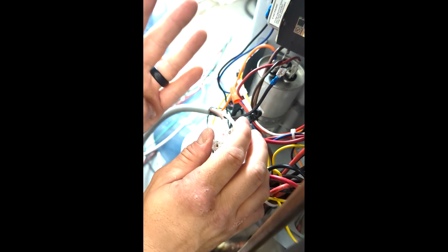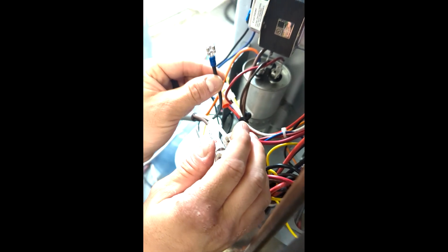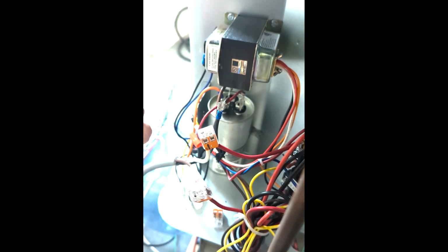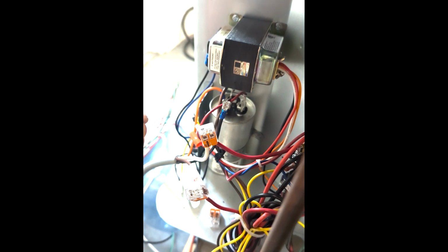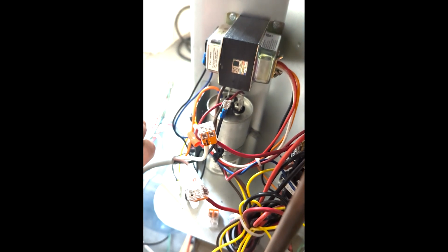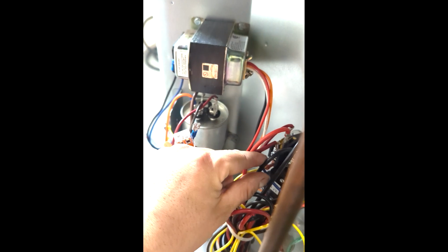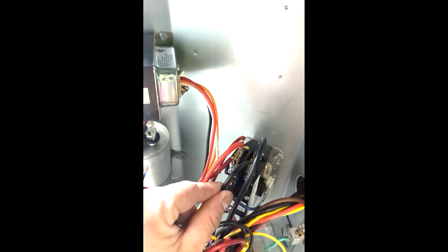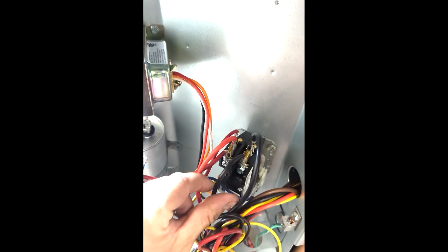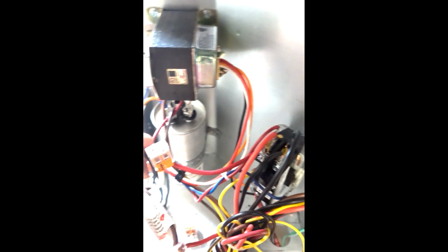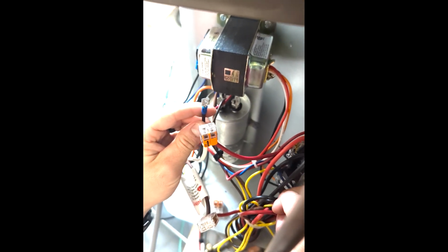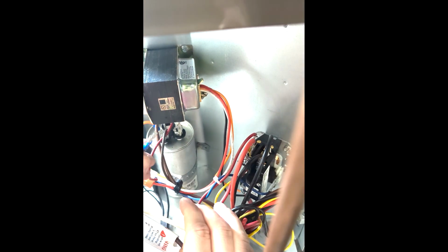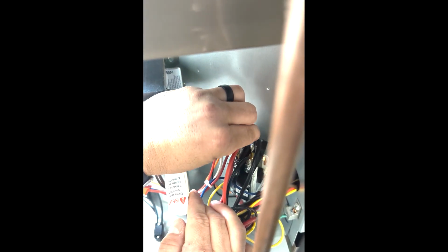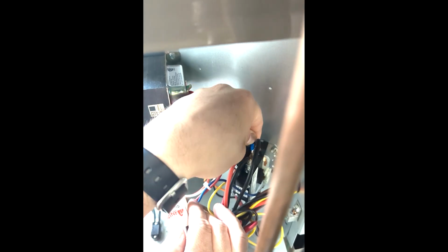Now, out of the four wires, you have one left, which is your black wire. So you go back to the compressor and follow the last third wire, which is usually a black wire from the compressor. That will usually land on your T1 terminal on your contactor. A lot of times, the reason we put this spade connector on here is because there's an empty terminal on your contactor, which I can see back here. So you just take the black wire, plug it onto there, and now you're set. You're all wired up, that simple.